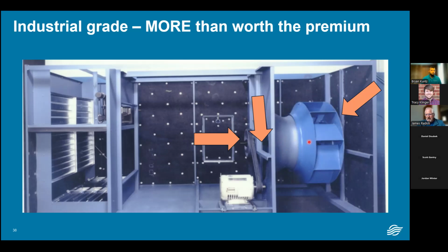And then that third arrow all the way over to the right is showing the type of airfoil fan we use on our industrial equipment. It's an airfoil fan wheel. Airfoils are quiet. They're most efficient. Those two things go together. If you're spinning a wheel and you're not moving air, you're making noise. So it stands to reason the more efficient, the quieter it's going to be.